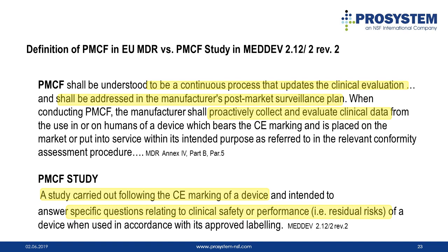Don't panic if you hear PMCF, since in the EU MDR, a PMCF does not necessarily mean that you have to conduct a clinical study. MDR defines PMCF as a continuous process that updates the clinical evaluation and shall be addressed in the manufacturer's post-market surveillance plan. So, we know that PMCF is the main source of clinical data in the post-market phase and is part of the PMS system.